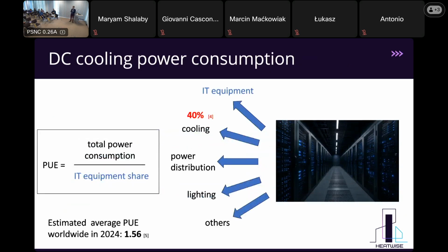But what about this energy which data centers are using? This is not only consumed by the IT equipment. There's also an overhead which is necessary to maintain the data center operational, for example cooling, power distribution, lighting, etc. So the average global estimate of the percentage of energy used for cooling is close to 40%. On the left side, I've put the formula for the well-known coefficient PUE, which stands for power usage effectiveness. In short, it gives us a clue about the size of the overhead a data center needs. So for example, if an object has a PUE of 1.5, we know that the overhead energy is close to 50% of the energy used by the servers alone.